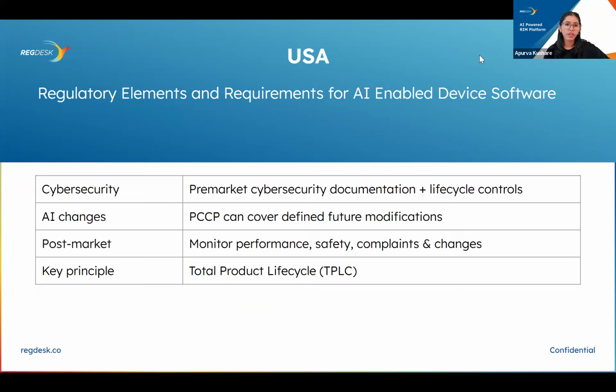Moving on to the next slide, we have some more elements to talk about, which are cybersecurity, AI changes, post-market, and some key principles. As part of the quality system for medical devices, including AI-enabled devices, manufacturers should have a post-market performance monitoring plan to help identify and respond to changes in performance in the post-market setting. Also, the total product life cycle of AI-enabled devices includes collecting evidence to evaluate whether a device benefits all relevant demographic groups, such as race, ethnicity, sex, and age, to help ensure that these devices remain safe and effective. So these are some key elements that we discussed for the software as well as the AI-enabled devices that manufacturers should take into consideration and must comply with.